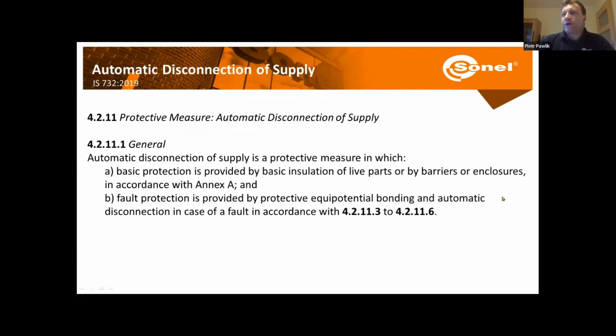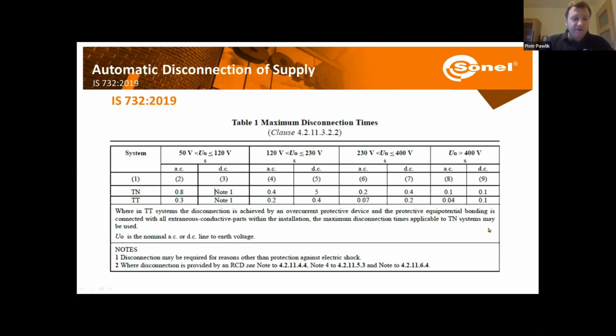Okay, so now in the IS 732, we have described different types of protection. And in case of a single fault, so a single short between phase and ground channel, we have the automatic disconnection of supply. So that means that the power supply should be disconnected. Well, what is the time for the disconnection? Again, we're going to look into IS 732. And depending on the type of the system that we have, on the level of the supply voltage that we have, we are going to have different times.